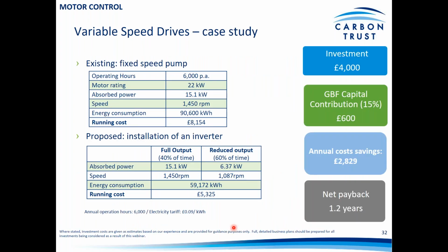So just looking at a brief case study here on variable speed drives. We've got an example here of a fixed speed pump operating at the top here for 6,000 hours per year. It has a motor rating of 22 kilowatts, but runs with an absorbed power for its duty of 15 kilowatts. That means that it runs at a constant speed of 1450 RPM, and overall that'll continue at that output across the 6,000 hours, consuming 90,600 kilowatt hours in the year, and that will give a cost of £8,150.